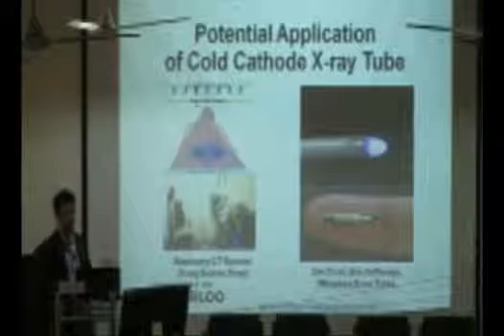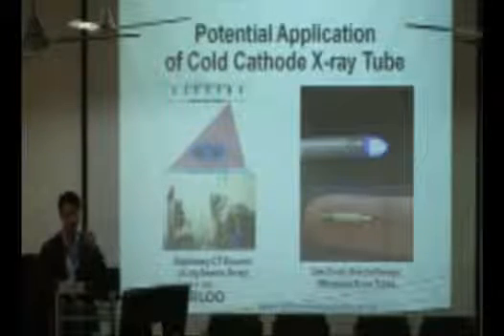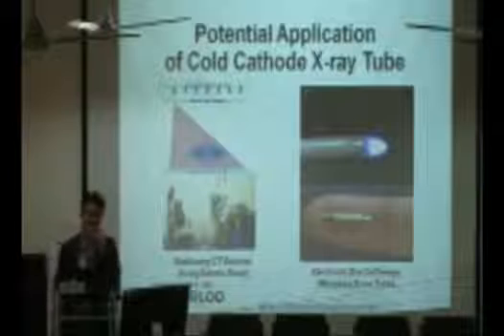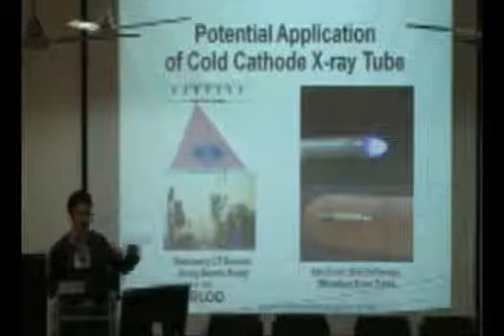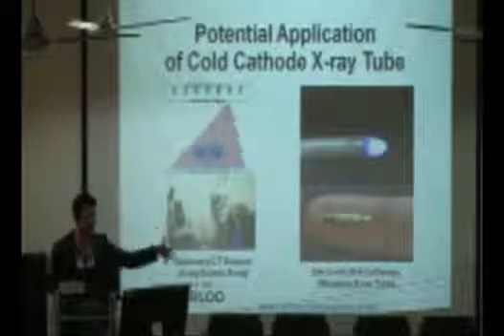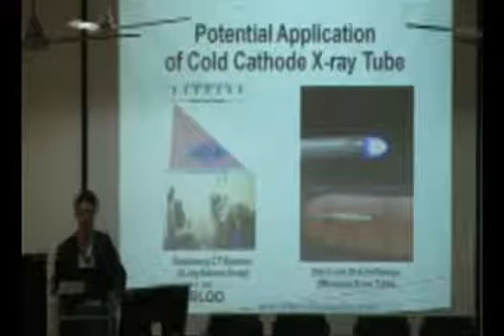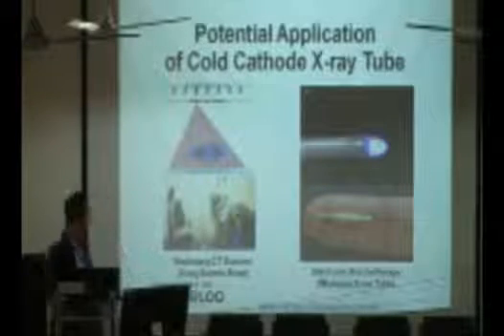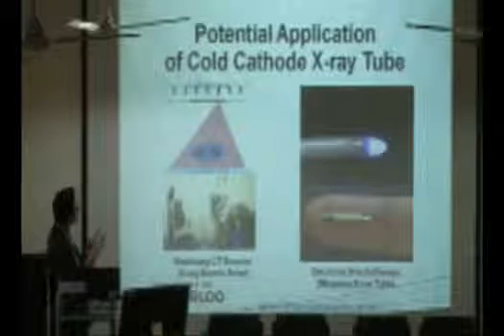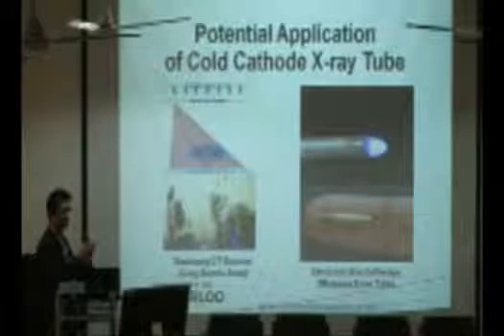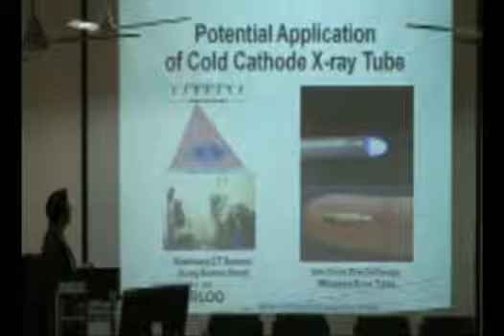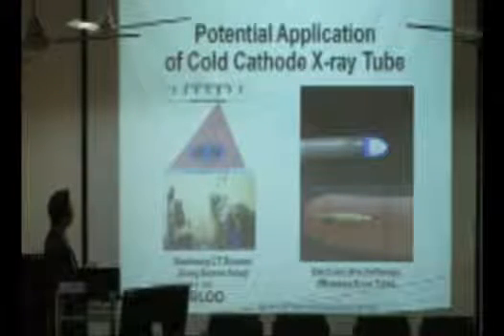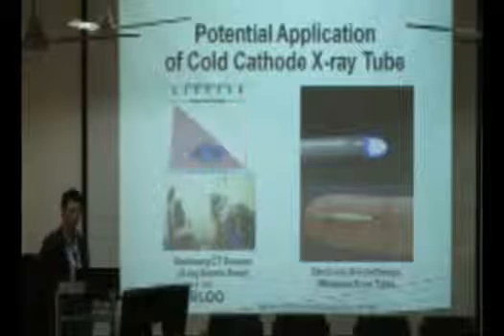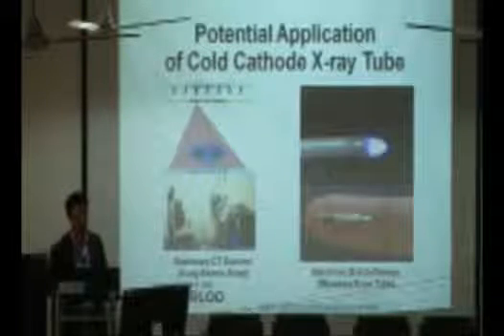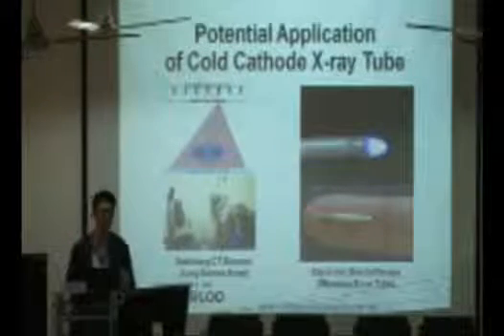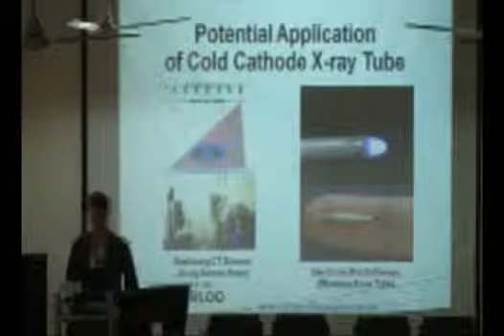Now, this concept is very different from the conventional CT machine that you just saw. Because in the conventional CT machine, we only have one X-ray generator that is moved around the patient on a mechanical gantry. Now, what we are suggesting here is if we could miniaturize the X-ray generator, then on a plane, we could have multiple X-ray generators. So what we are proposing is a solid-state CT machine without any mechanical gantry at all.